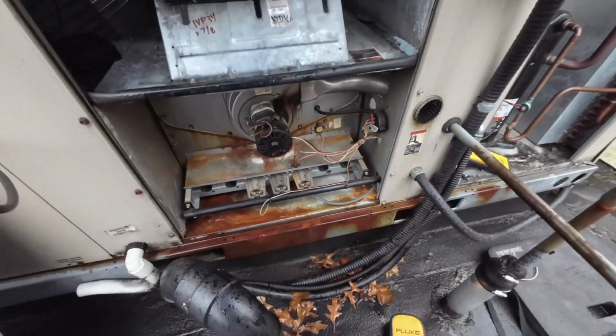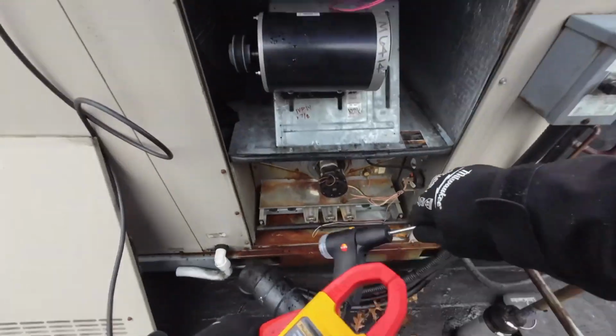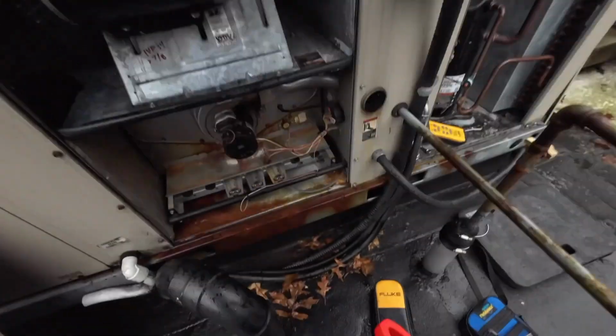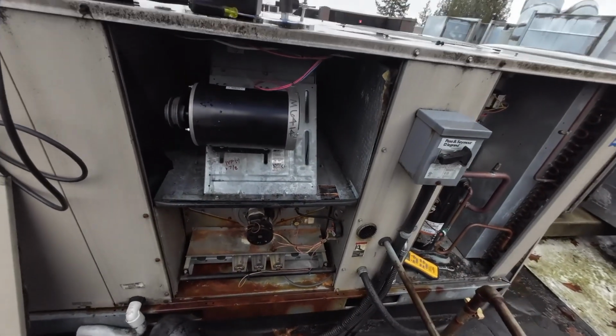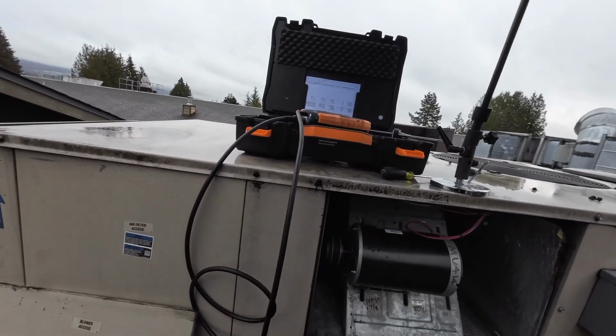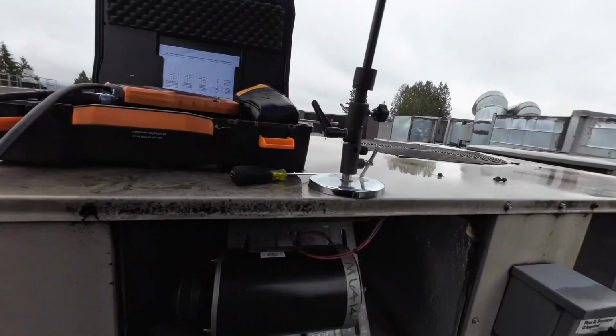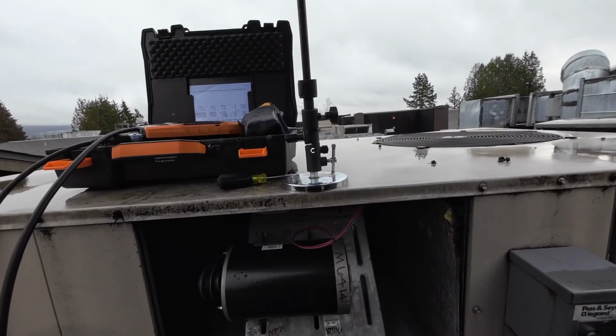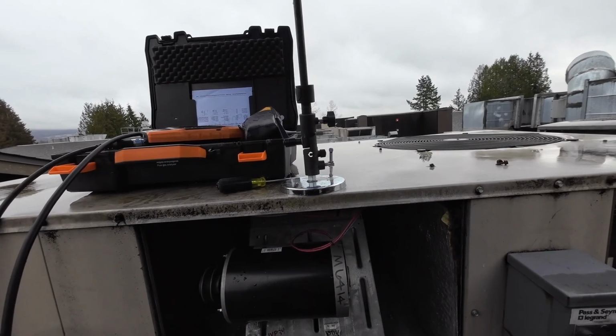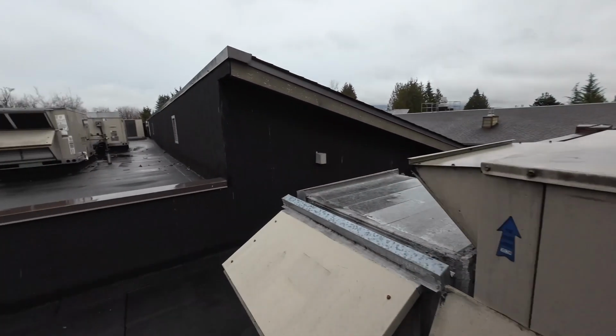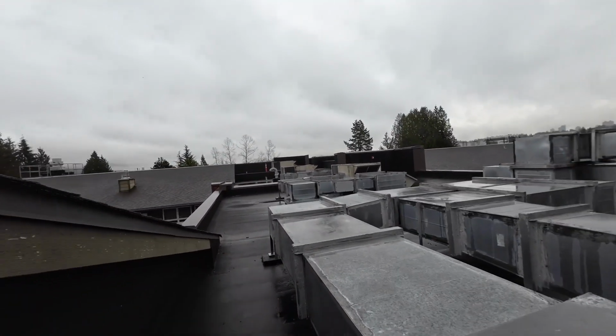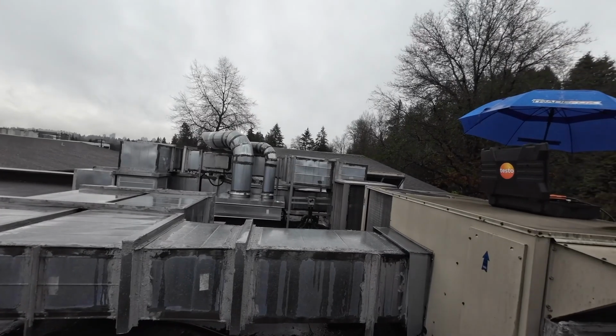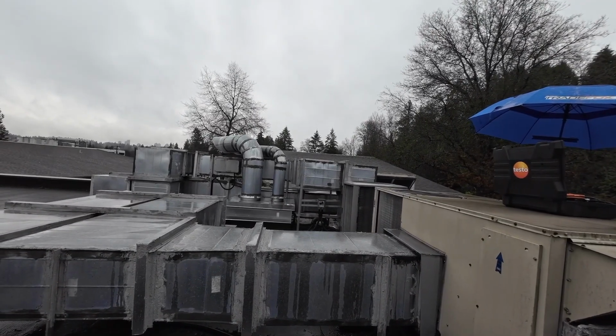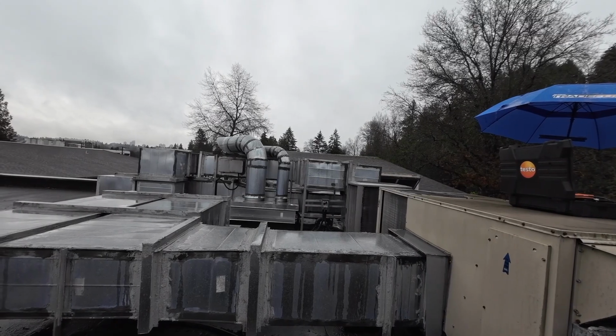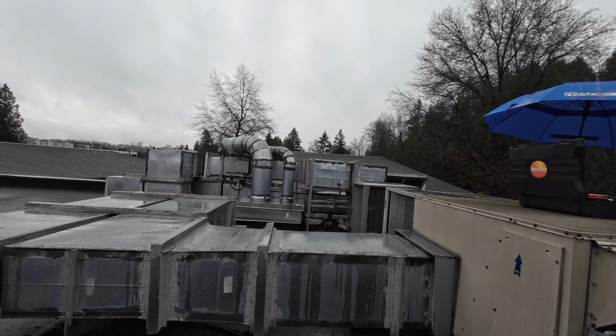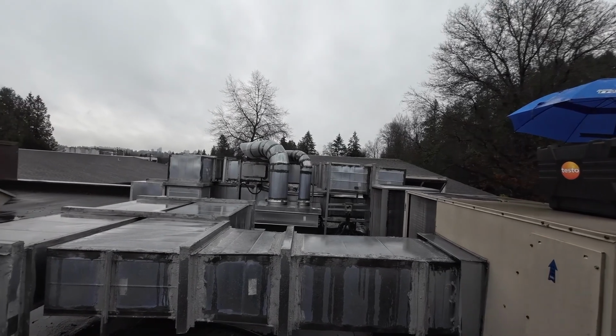Next thing I can do is drill a hole in the ductwork there and really confirm that. So I guess I'm gonna do that. I'm gonna punch a hole in the side. I don't know if it's got a cracked heat exchanger, because I can't get to it. So this is what I've got to play with. I think I'm going to punch a hole in there and see if we got any CO going into the space. And if we do, then we need to get a new heat exchanger.